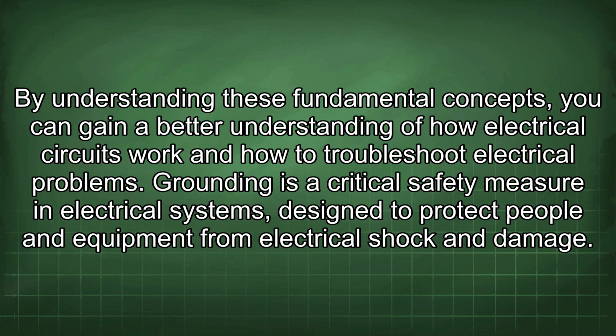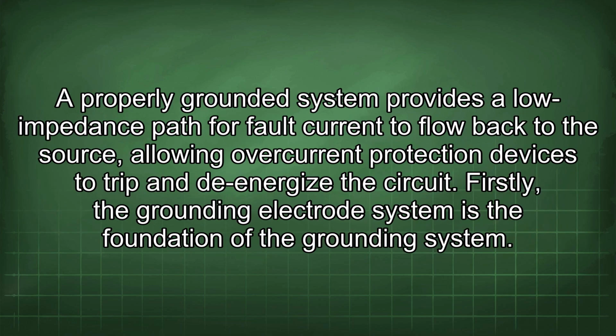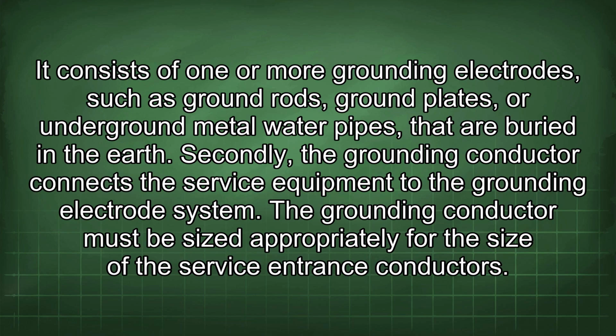electrical problems. Grounding is a critical safety measure in electrical systems, designed to protect people and equipment from electrical shock and damage. A properly grounded system provides a low impedance path for fault current to flow back to the source, allowing overcurrent protection devices to trip and de-energize the circuit. Firstly, the grounding electrode system is the foundation of the grounding system. It consists of one or more grounding electrodes, such as ground rods, ground plates, or underground metal water pipes that are buried in the earth.